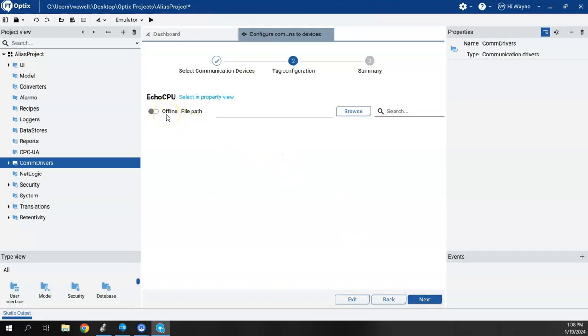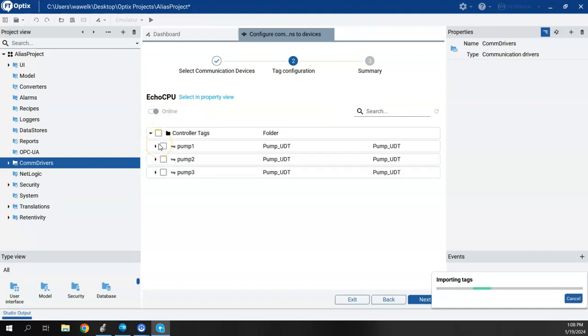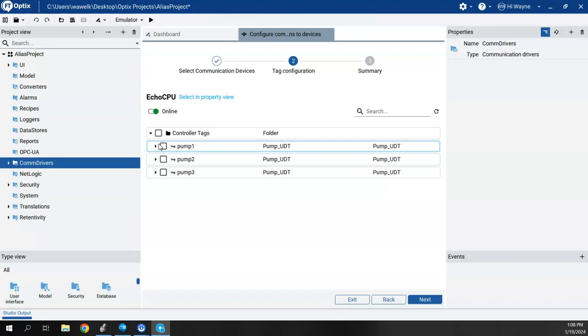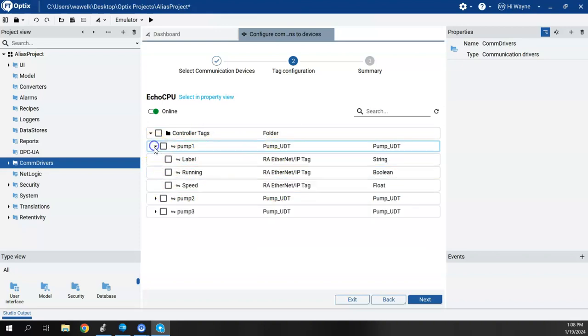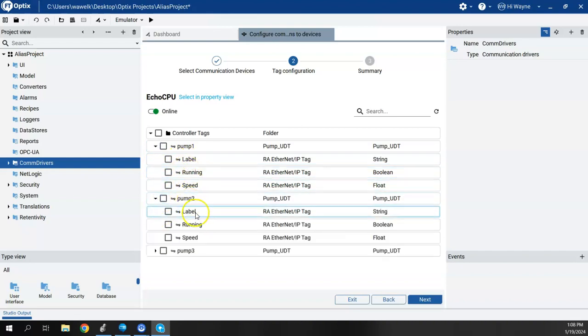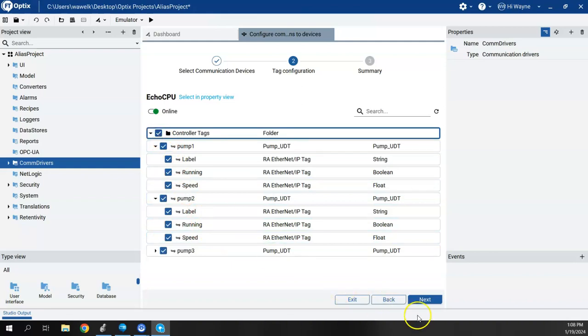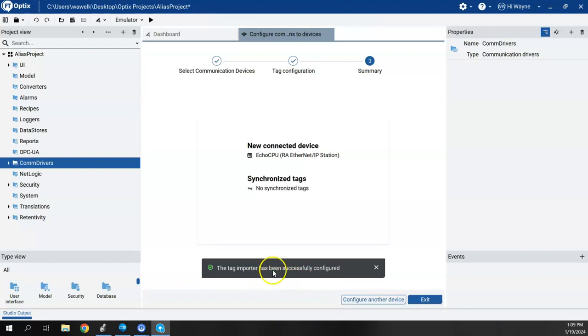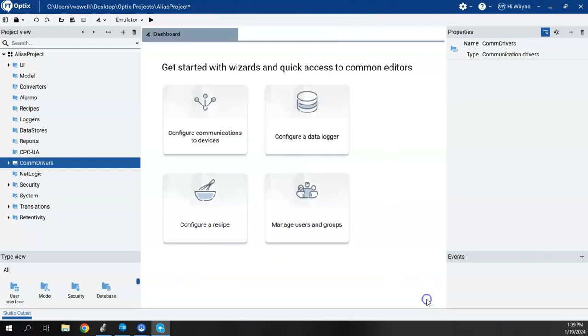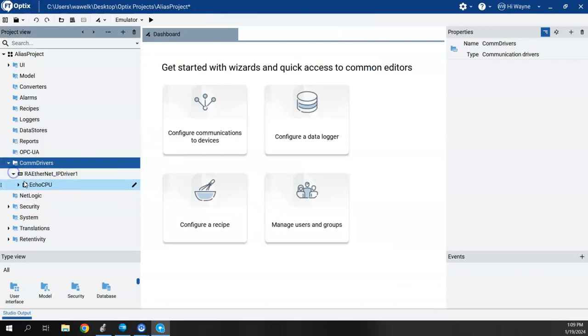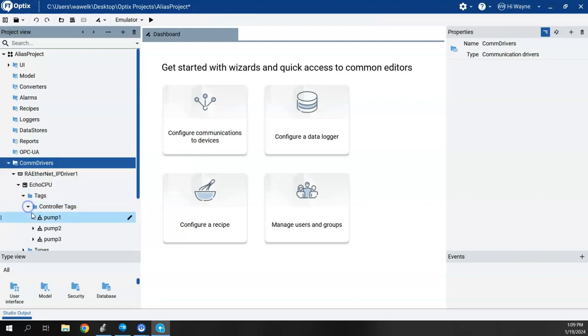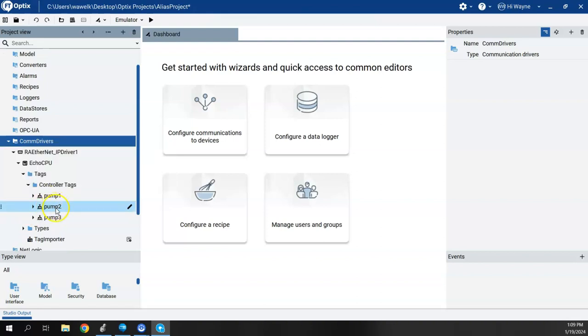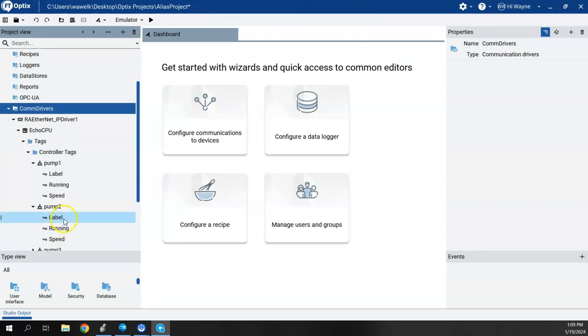Now I have choices to import my tags — either offline by connecting to the ACD file, or online by connecting to the real running controller. I'll choose online. It found the controller tags: Pump One, Pump Two, and Pump Three. Expanding them shows all the sub-tags are there. I'll select all and click Next. That successfully imports the tags. Under Com Drivers, I can see the driver, station, and tags — controller tags Pumps One, Two, and Three, each with label, running, and speed.